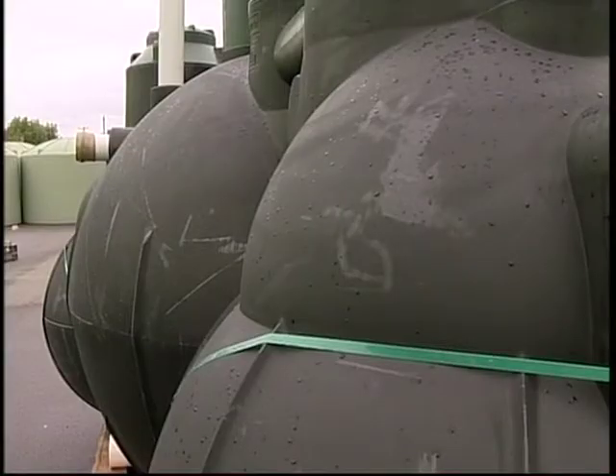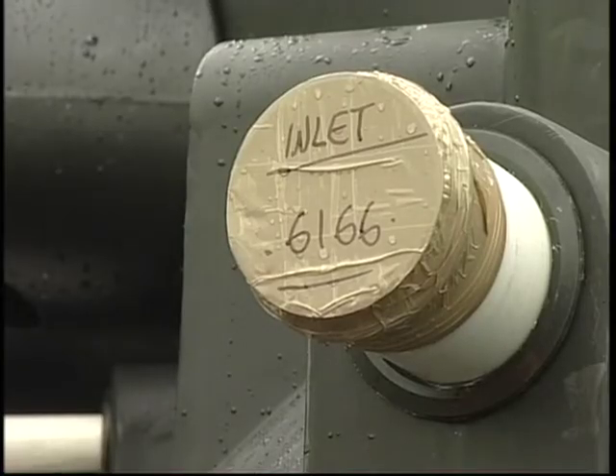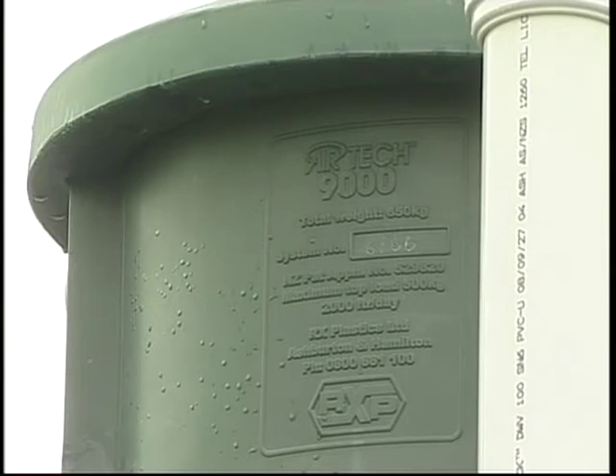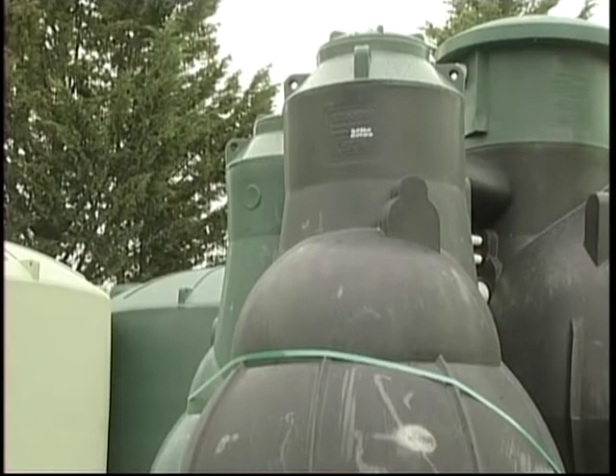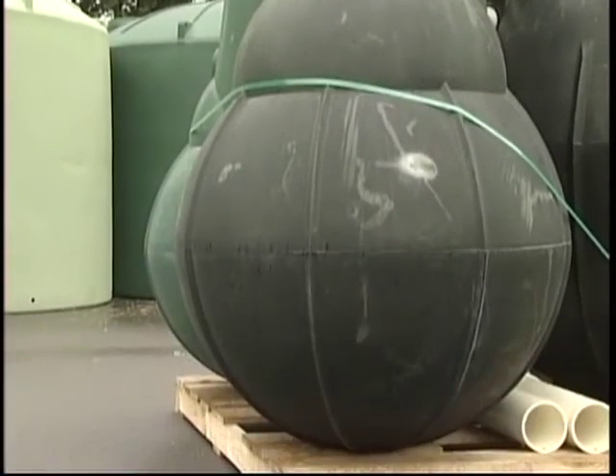So what can you put down it? That's a really good question, because they aren't a giant hole in the ground that makes everything go away. A basic rule of thumb — if you can't eat it, don't flush it down there. Waste disposal systems are a no-no in any of the brands of aerated treatment systems, because it's untreated vegetable matter that sinks in the bottom of the tank and builds a sludge that would have to be pumped out quite frequently.